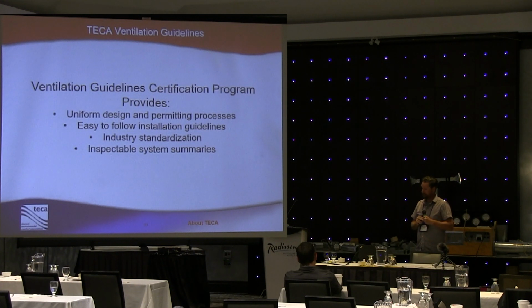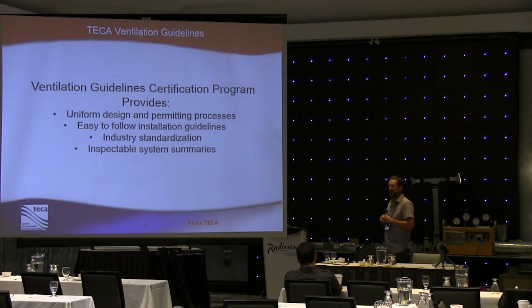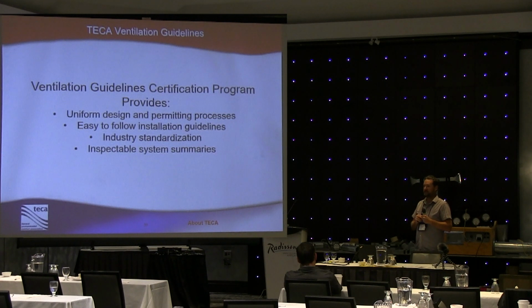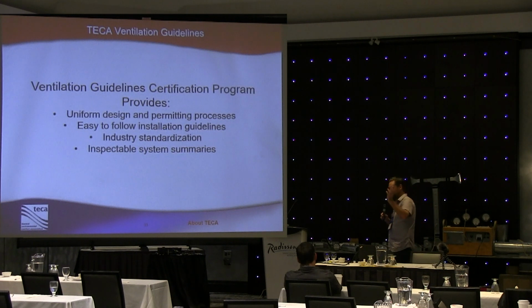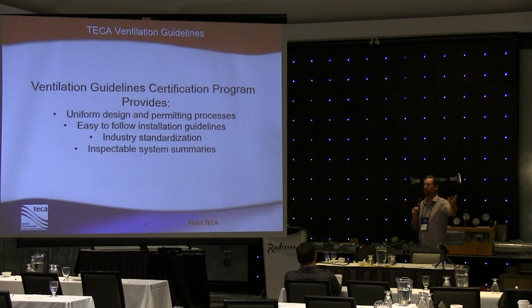Outside of that, I think the more scrutiny you have when you're looking at these applications, and the better job that gets done on site, is going to make sure that these ventilation systems are coming together the way they're supposed to, right? It's tricky though, especially if you've got a contractor that has run all of his ductwork based on the sizes on his worksheet, but he's got more length and more elbows, and maybe he's not sizing correctly.